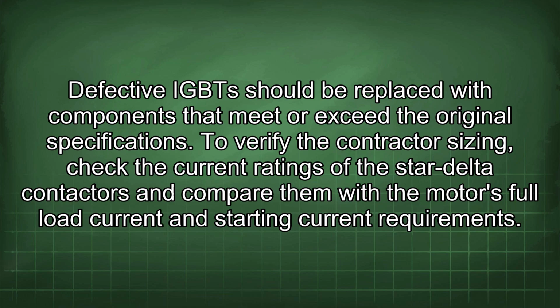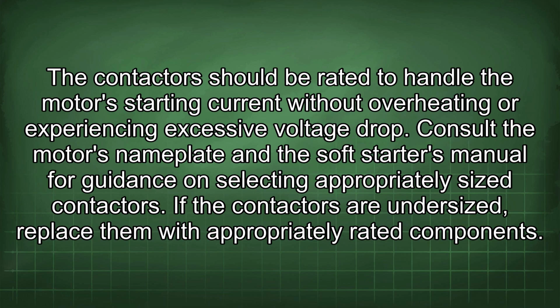To verify the contactor sizing, check the current ratings of the star-delta contactors and compare them with the motor's full load current and starting current requirements. The contactors should be rated to handle the motor's starting current without overheating or experiencing excessive voltage drop. Consult the motor's nameplate and the soft starter's manual for guidance on selecting appropriately sized contactors. If the contactors are undersized, replace them with appropriately rated components.